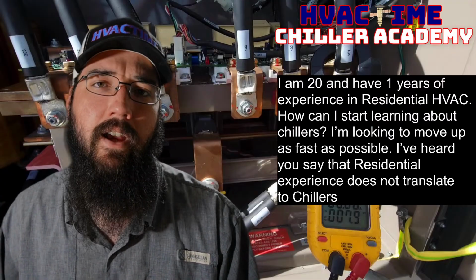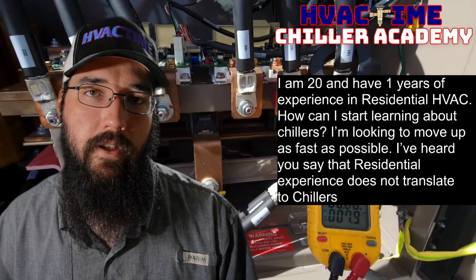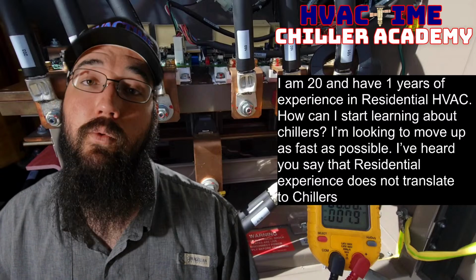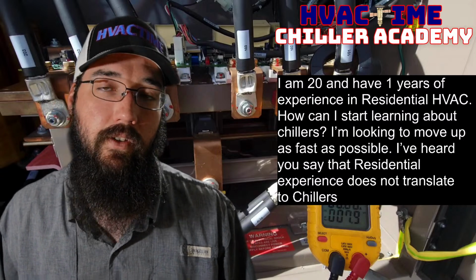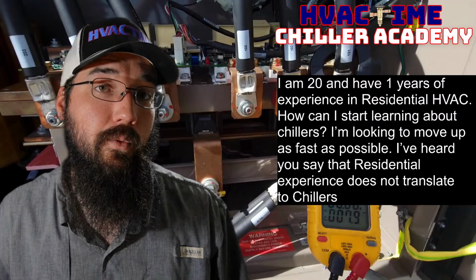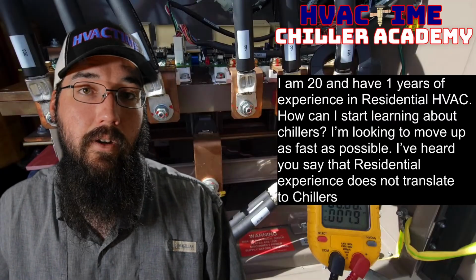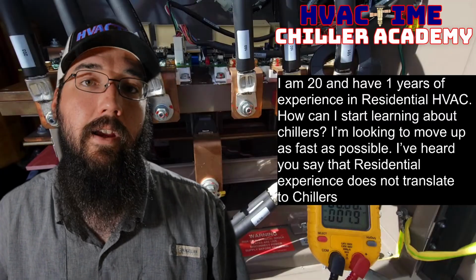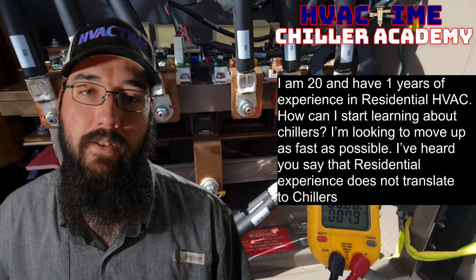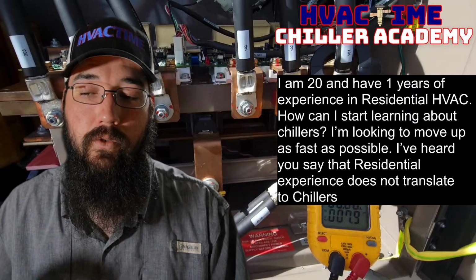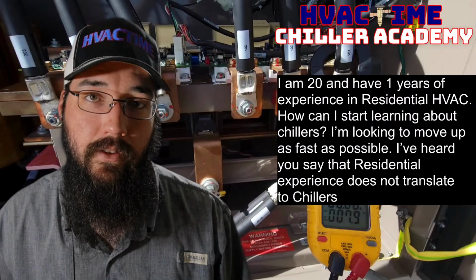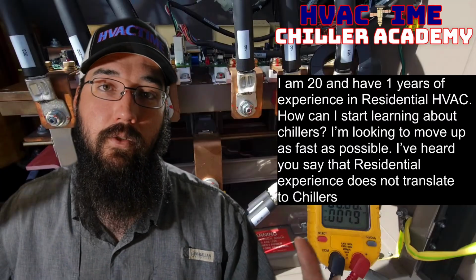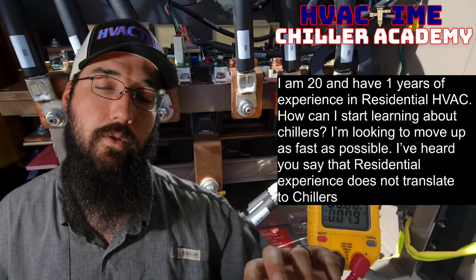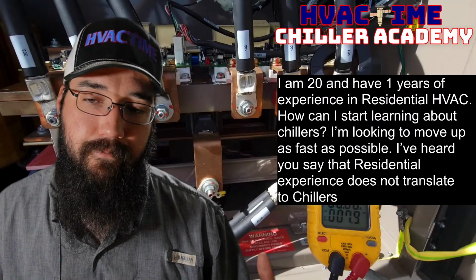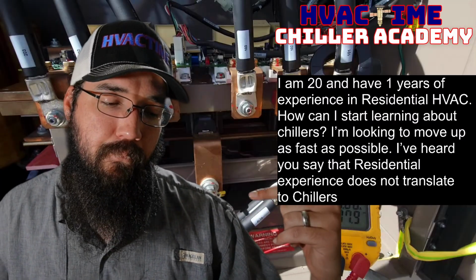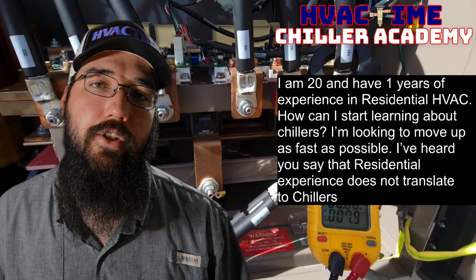Why do we have that? So that we can run colder leaving water temperatures out of our machines without freezing the water, because water freezes at 32. Sometimes we need to run at 30 or the upper 20s in terms of temperature to achieve whatever process is happening, right? Those systems exist. So we have a brine solution, or maybe we just don't want it to freeze due to ambient conditions too. That also is true. Either way, that's what a chiller is.